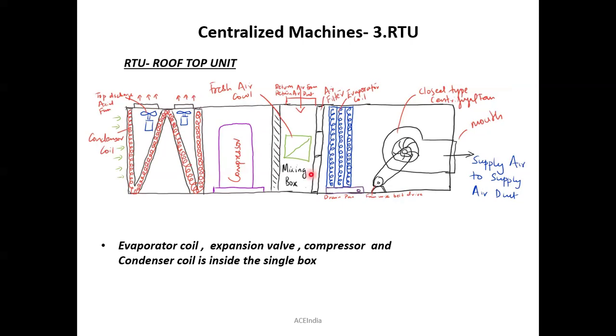Right now, you can see this kind of condenser arrangement is termed a V-type arrangement. And here, it is not a side discharge axial fan. This whole arrangement of axial fans is termed a top discharge type. Okay, what is this type? Top discharge axial fan type. So the heat is absorbed from the atmosphere and rejected in a top-wise manner itself. Okay, guys, good to go.